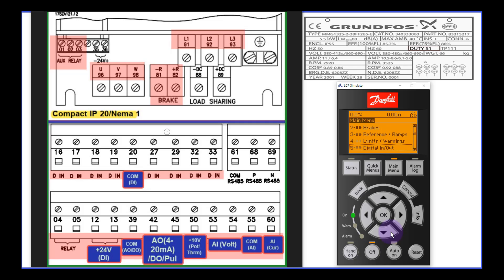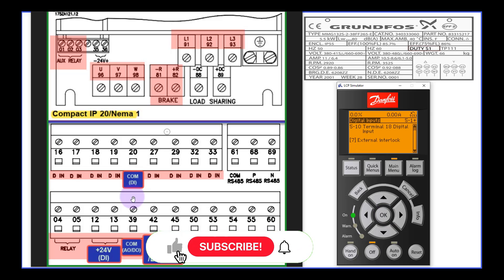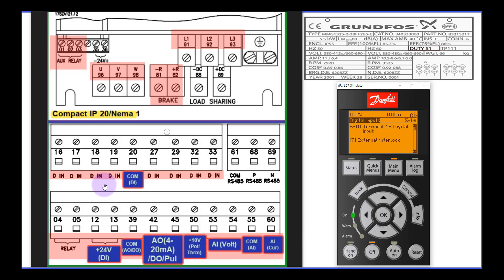Press the down button until you see 'digital input output,' then press the OK button. Press the down button to select 'digital input,' then press OK. I have a toggle switch I will use to start my motor. I will connect my toggle switch to terminal 18 and terminal 20. I press up/down until I see terminal 18 digital input, then press OK to make changes. I will use this as a start toggle switch, so I press the up or down arrow key until I see 'start,' select it, and press OK to accept.